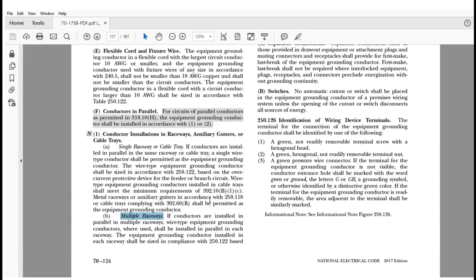And remember, we're talking about a single raceway or single cable tray where the conductors being run in parallel are in that cable tray or single raceway. It says wire type equipment grounding conductors installed in cable trays, because the first one was raceways, in cable trays shall meet the minimum requirements of 392.10(B)(1)(c). So you have your requirements there that have to be met.